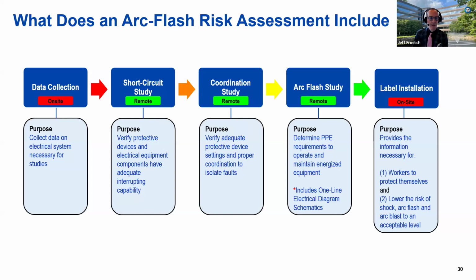It's going to verify the protective devices and electrical equipment components have adequate interrupting capabilities. They'll get into equipment parameters like voltage, impedance, power rating. They'll look at all the fault scenarios. They're going to run calculations of short circuit currents for different fault types. They'll do analysis of the protective devices and those fault types, phase to phase, phase to ground, 3-phase, different types of asymmetrical faults, and make recommendations.